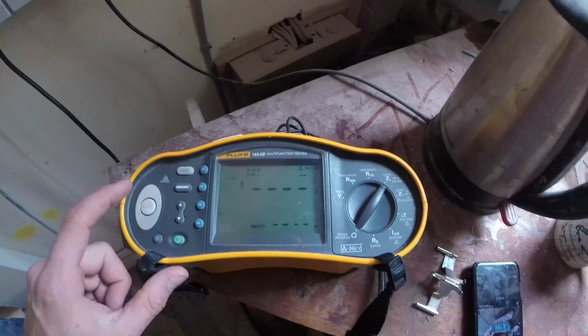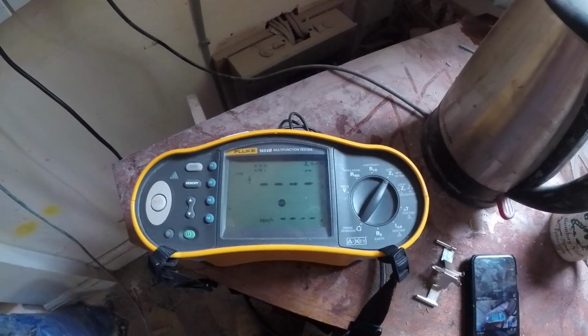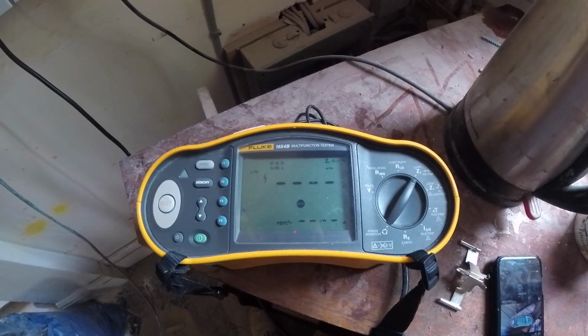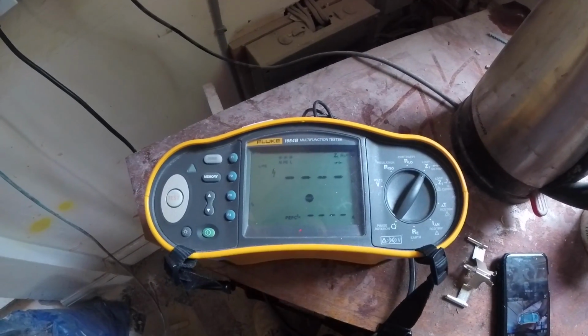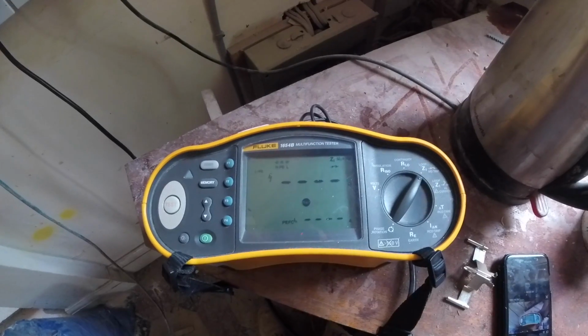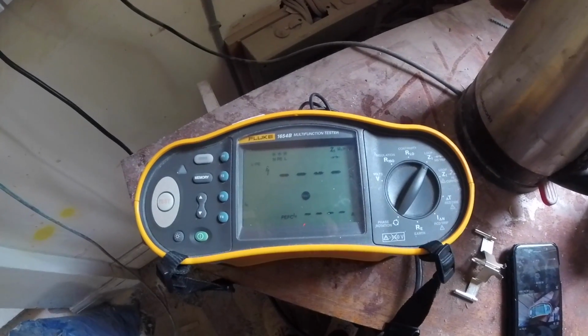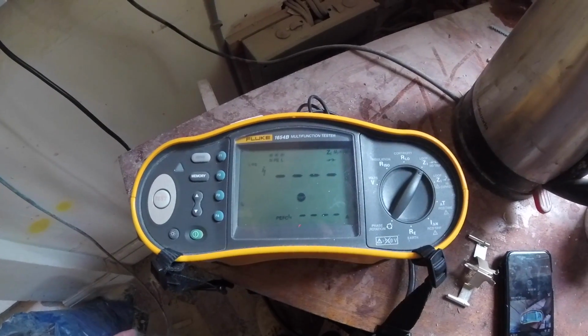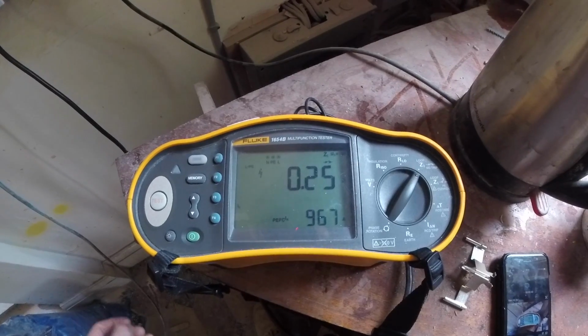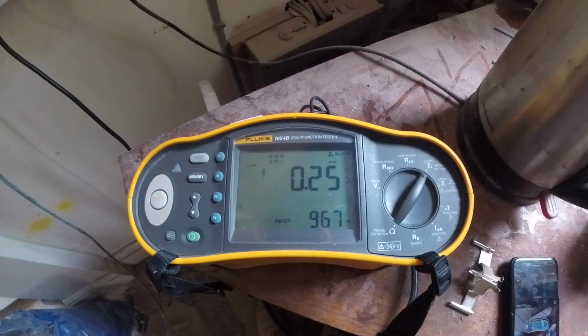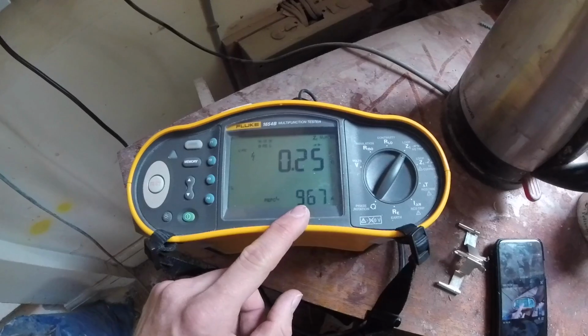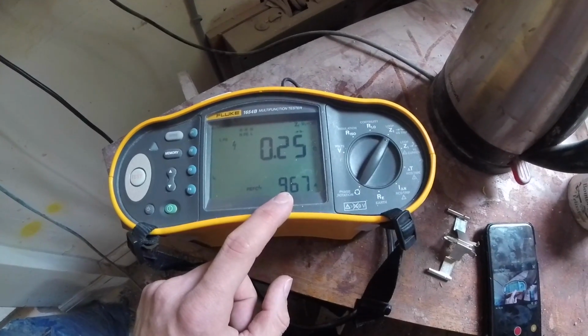So all you have to do on this is press test. Now, because it's doing the no trip test, it does take a bit longer than the high current one. One of the pros of this unit is it doesn't take too long at all, really. I think there are meters out there which are a bit quicker, but there you go, it's up there already, 0.25. Down the bottom it gives you your prospective fault current down there as well.